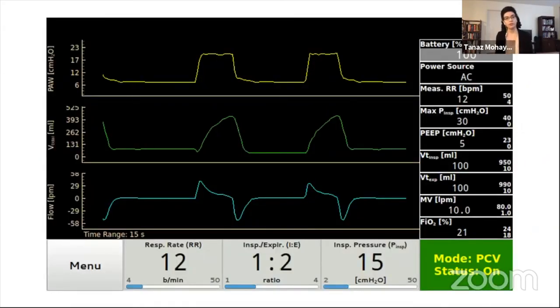So the waveform I showed earlier was to give you an idea of how pressure and flow waveforms change in PCV and PSV modes. As to what the MVM waveforms look like, here's an example snapshot of the pressure waveform on top, volume waveform in the middle, and flow waveform at the bottom. That's how things are shown for the PCV mode on the touchscreen display.